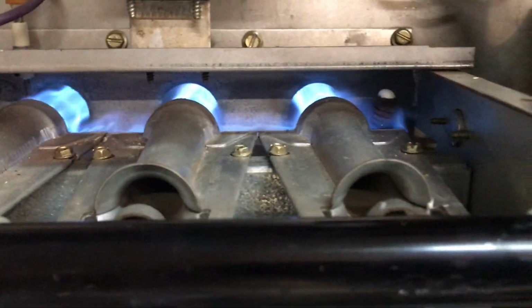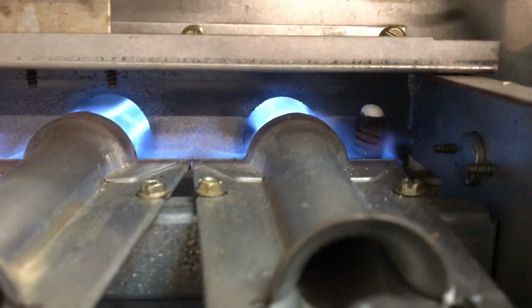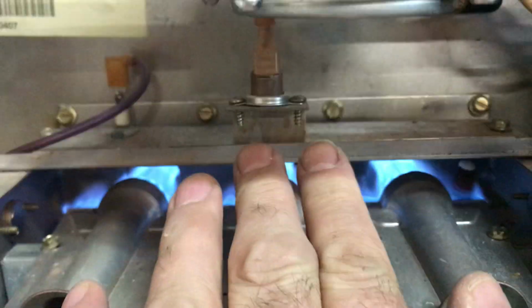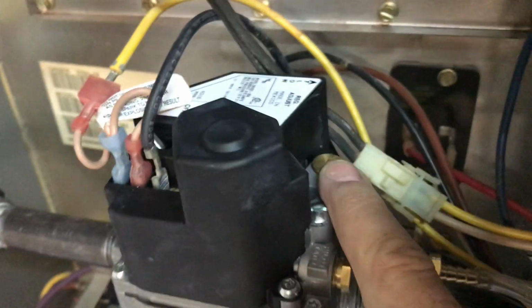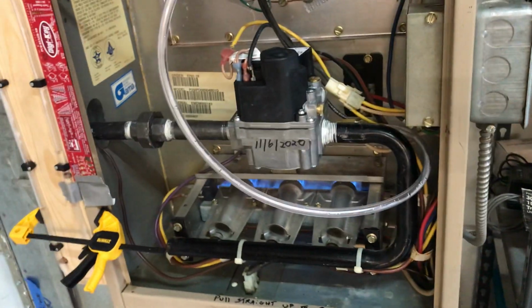Whether it makes any difference, 3 inches water column seems to put enough gas through here. I don't see much leaking. It's hard to say whether it's going to trip this out. Well, I know it hasn't, because it just said it. And it backed off a half turn from the factory, and it seemed to be okay all night. So we'll go over and look at the paperwork, and you'll see this is a universal gas valve.